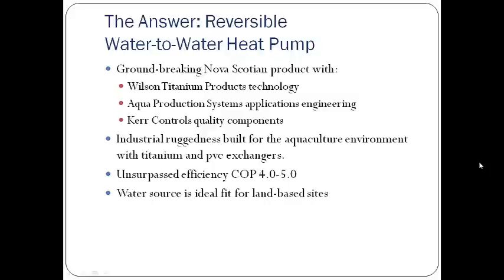Coefficient of performance 4 for cooling, 5 for heating. The coefficient of performance is a measure of efficiency. In refrigeration, you can pay for, say, 1 kilowatt of electrical energy and transfer 4 to 5 kilowatts of heat energy. So rather than have an efficiency of 400% or 500%, we use the unit coefficient of performance to measure the efficiency of refrigeration equipment. And the water source was chosen as an ideal fit for aquaculture applications. Water coming in means water's leaving.